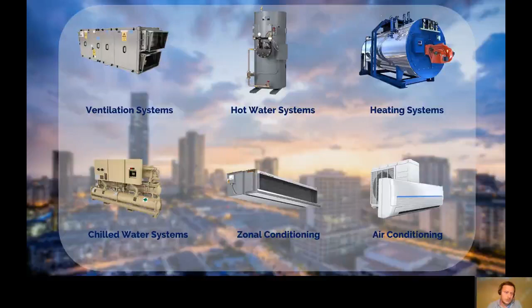So what would be the drivers behind that? Well, comfort - we have to provide a pleasant environment for the end user, the occupants. Productivity - providing a better environment would increase the occupants' output. Energy - we could run everything full tilt, but from an energy perspective, it's not going to be very efficient. We have to be able to integrate with other communication systems, maybe like lighting, fire, access control. And then we have regulatory elements like L8, so things like Legionella checking and condition monitoring. It's important that from a BMS standpoint, we can manage all of that.